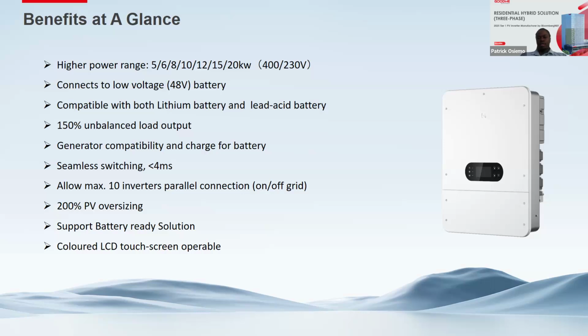Talk about off-grid. Sometimes you'll notice that you have a very small window of, let's say, supporting your house or even fully charging your batteries. Now, with the ETLV, you can oversize your solar PV capacity to be double the inverter rating. So 200% PV oversizing: for a 10 kilowatt inverter, you can connect up to 20 kilowatt peak of PV. This I will explain in the upcoming slides, but generally it's to allow you to support your house, the electrical loads, as well as charge your batteries efficiently and even faster.